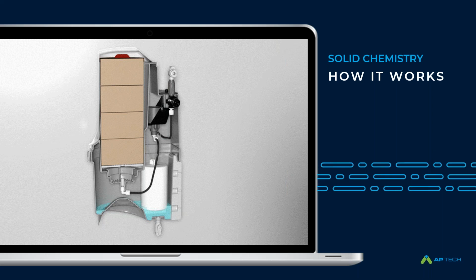We've got an inlet assembly on the upper right there with a pressure regulator. There's a level control valve with the white sand weight that's in there. And essentially, when that unit needs solution to be made, the water sprays, it contacts whether it's the disc form, which is represented here, or up into the bottle, rapidly dissolves the product, the chemistry.